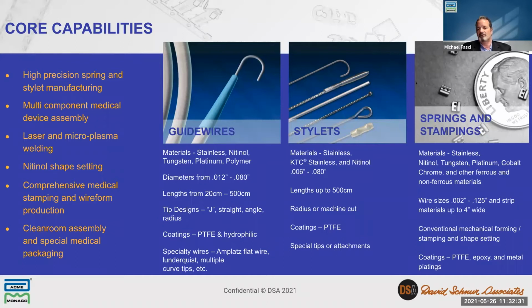For about a period of 10 years, we didn't see much change in the market until nitinol core guide wires became popular. These were initially adopted by our international customers and then slowly by domestic customers. This technology was very important because there were typically issues with guide wires in the field due to the wire kinking if it's incorrectly used by the physician, or if it comes up against some obstruction in the anatomy. The nitinol core wire makes it very difficult to kink the wire during use, and so that became a popular addition to our product portfolio.